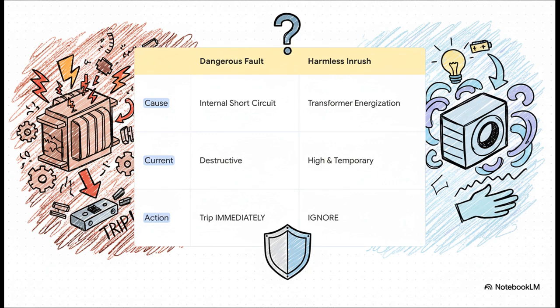The problem? To a simple protection system, they both look like a massive internal problem. But the actions you need to take are complete opposites. For the fault, you have to trip the breaker immediately. For the inrush, you have to ignore it, or you'll cause a false outage. So, how does the shield tell the difference?